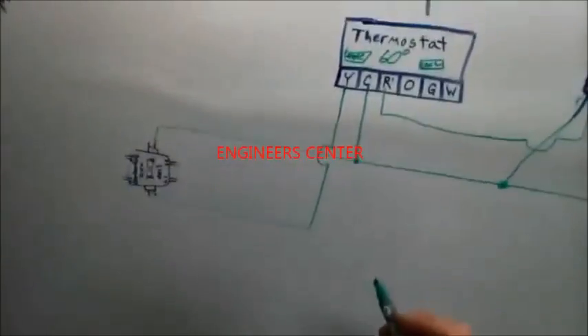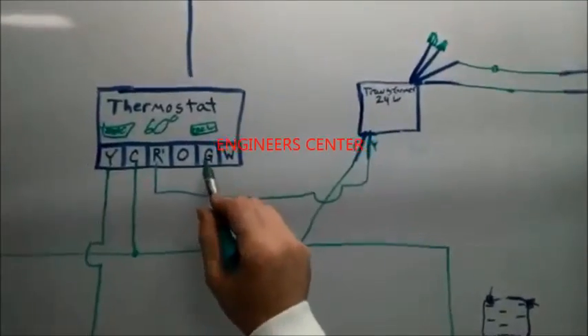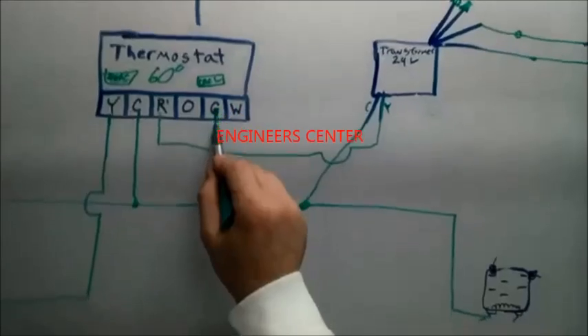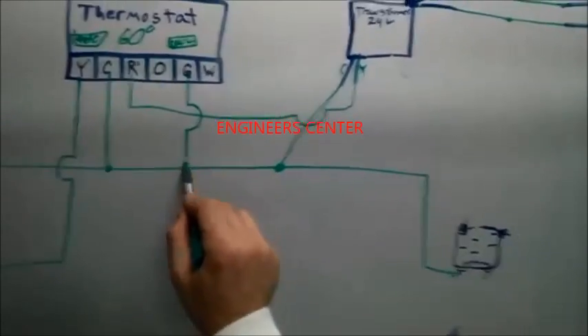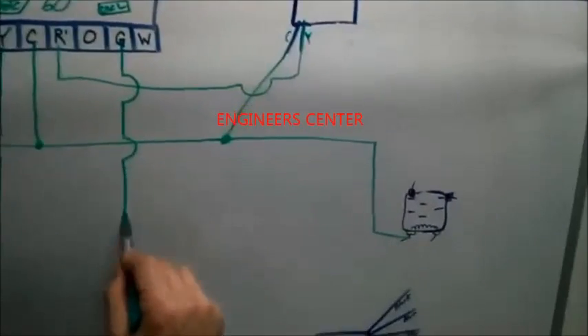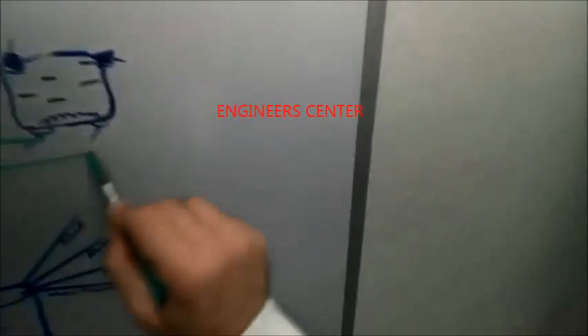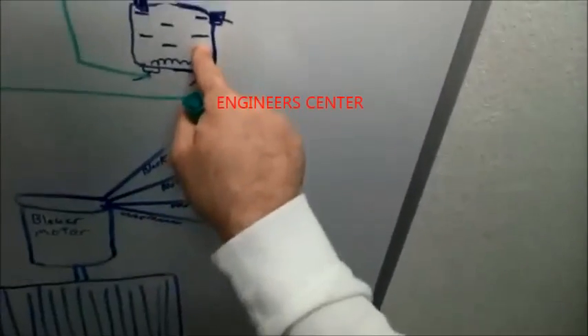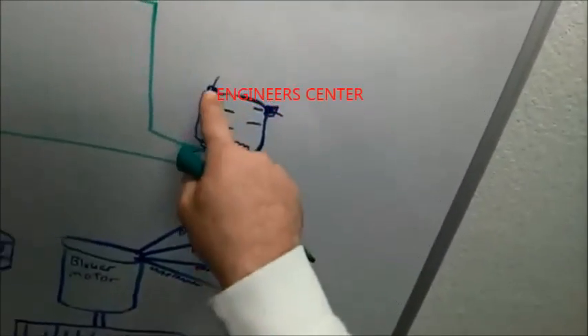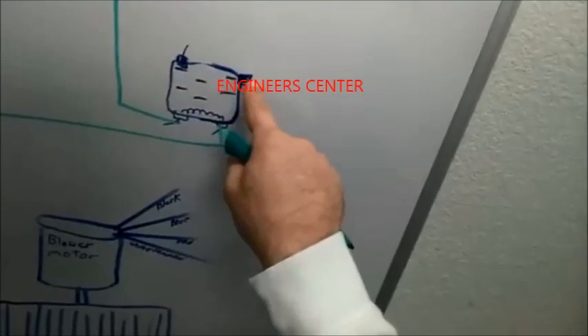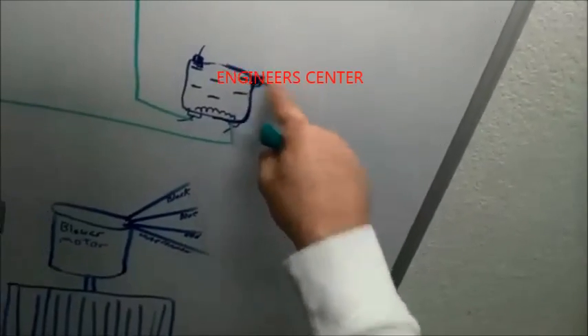So let's continue on. We would also be giving power out green, as I said, remember? Jump it, jump it. And that would want to come down here, and that would be closing your fan relay. And so if you had a line of power coming in here, it would now bridge to here, which we know we would send to our blower motor. So on this most basic of units, our low volt is done.